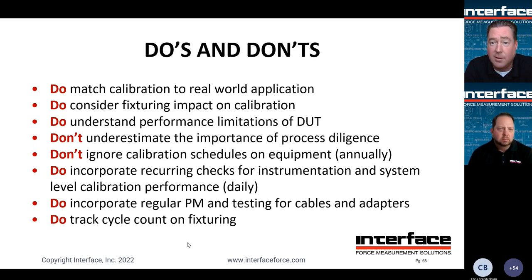That can consist of replicating fixturing up to and even actually using the customer's fixtures in the calibration rig, as Brian referenced. We've got experience doing that. Load pins immediately spring to mind specifically, but that can have great impact. Do consider fixturing impact on calibration. That also ties back to the first point, making sure that the fixturing is appropriate for the calibration type being used. Flat surface to flat surface in a compression type calibration would be one example of what not to do. If you're seeing something untoward in the calibration data, maybe it's worth going back and reviewing that calibration fixture to make sure that there's not a fatigue issue or some sort of a bend. Is it bent? Is there another issue with the fixturing that's impacting that calibration?